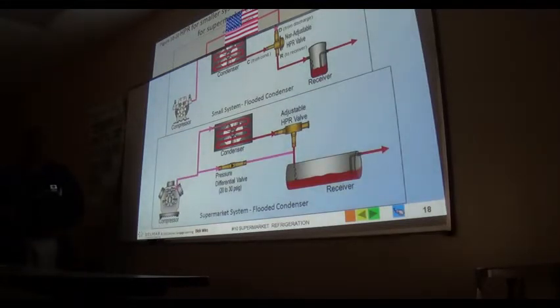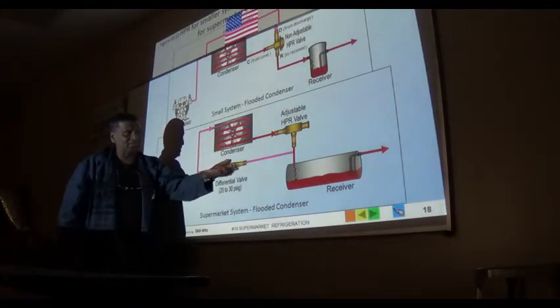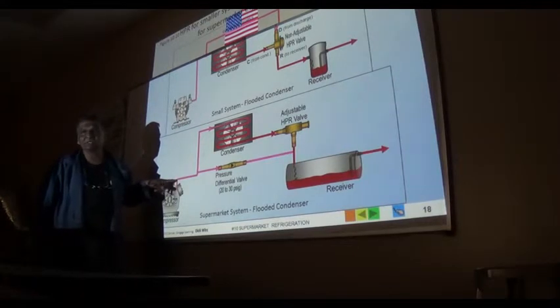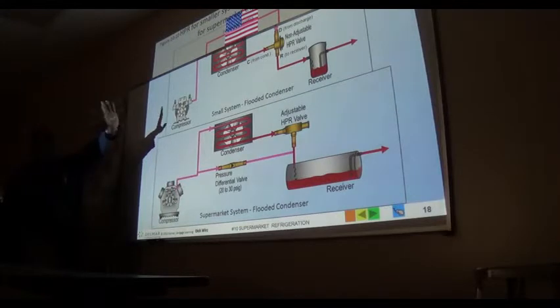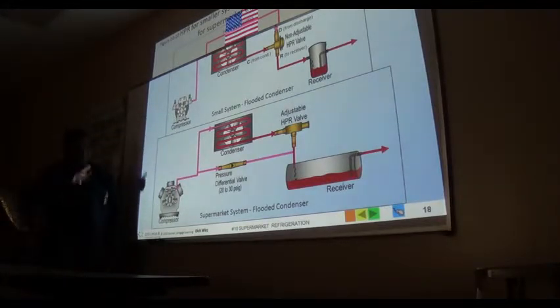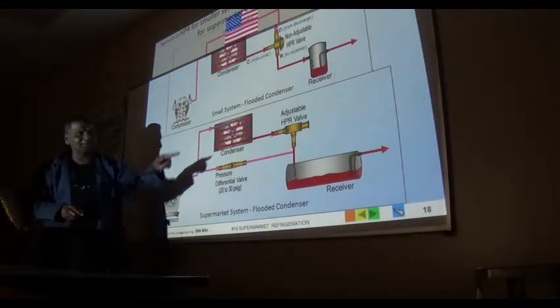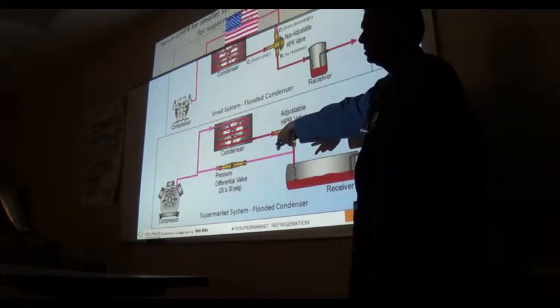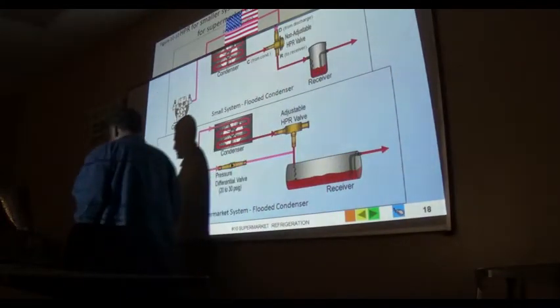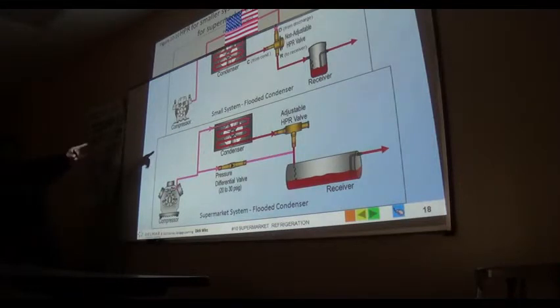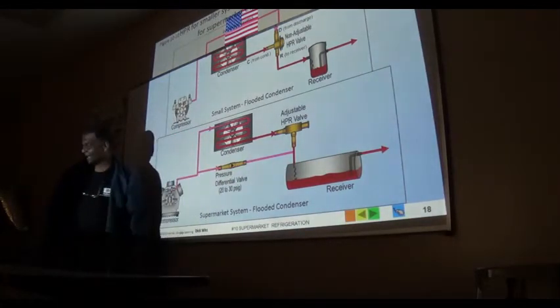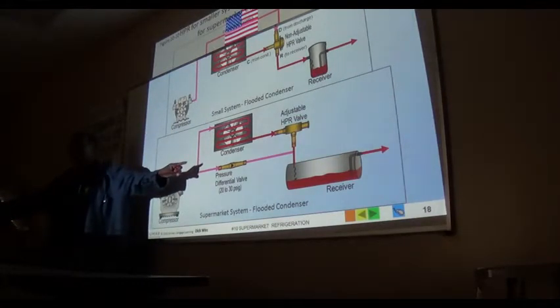And this one is adjustable. This is a pressure differential valve. That one is adjustable. And guys, you have to do this with your gauges on. Okay, that's self-adjusting. It's set for one pressure, and that's it. And believe you me, if you're new to this and you go out in the field, don't feel bad. If you see one of these and you suspect it's that, get a second opinion. This is one of the most difficult set of valves to diagnose as bad. Even the guys in Portland who made this go nuts when it comes to diagnosing problems with those two, because you never know for sure if it's this or that. So typically we end up changing both of them. And that's the one time I do not mind being a parts changer, because it's going to save me a lot of grief by changing both of them.